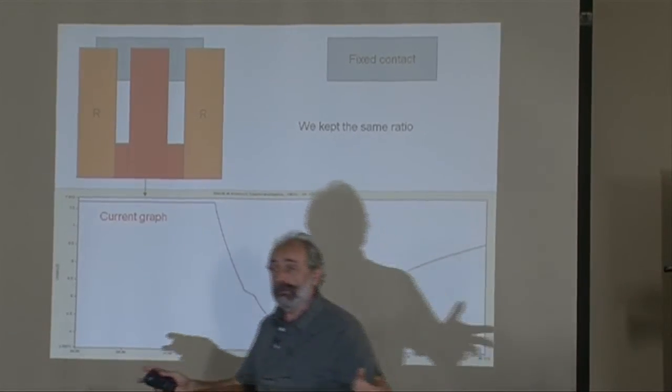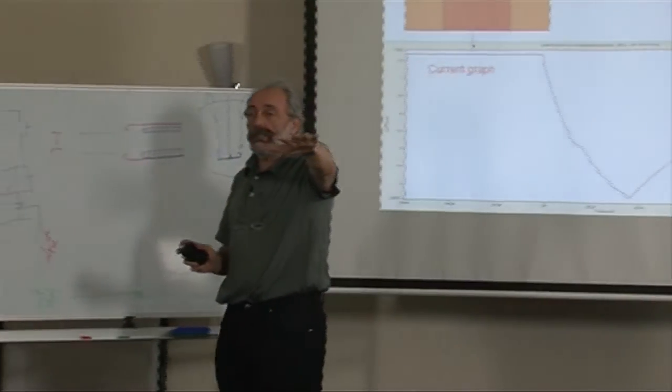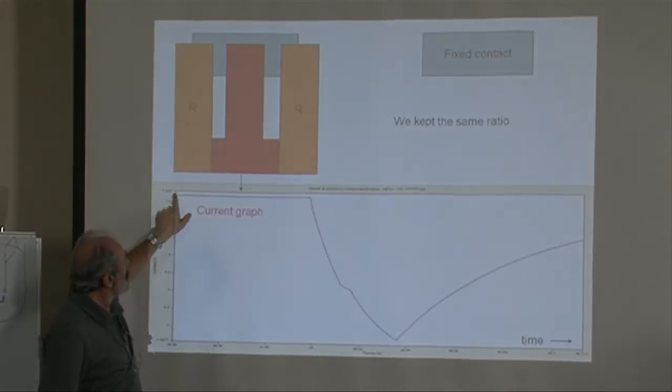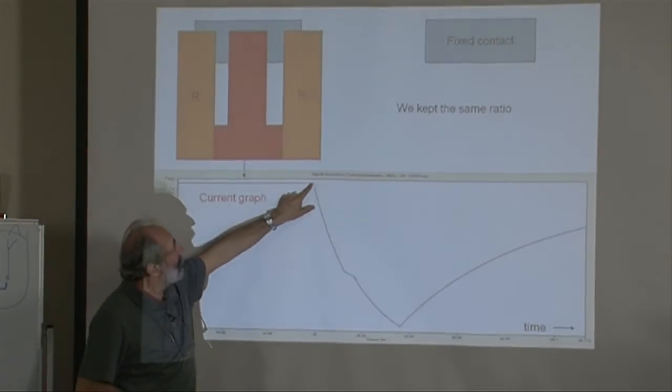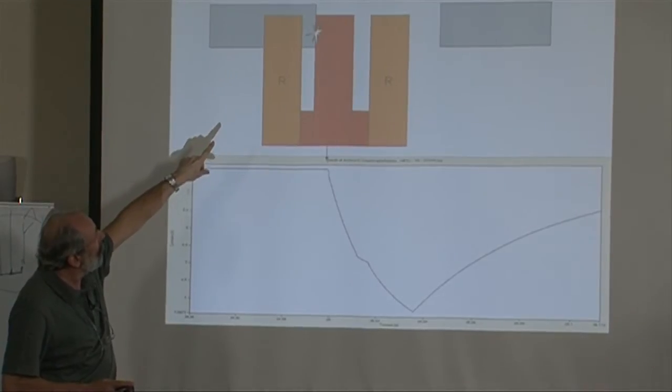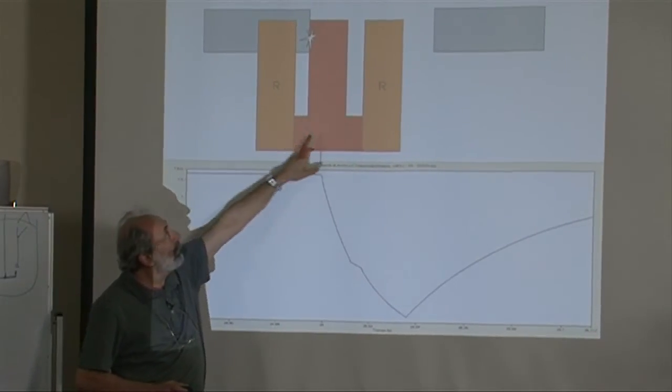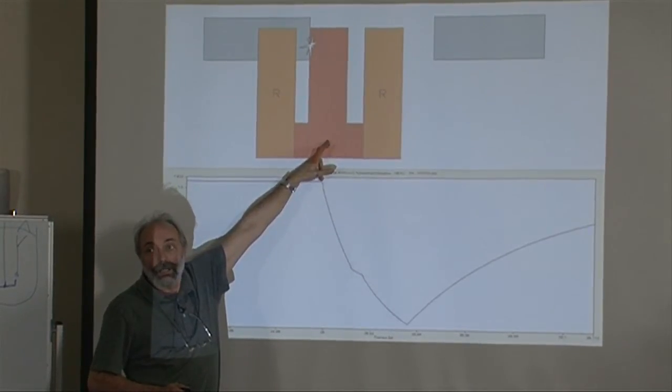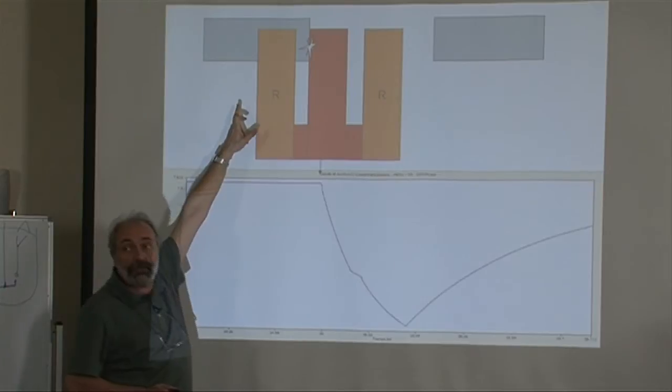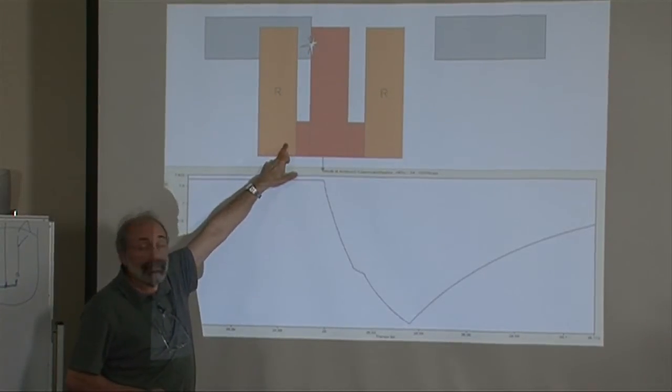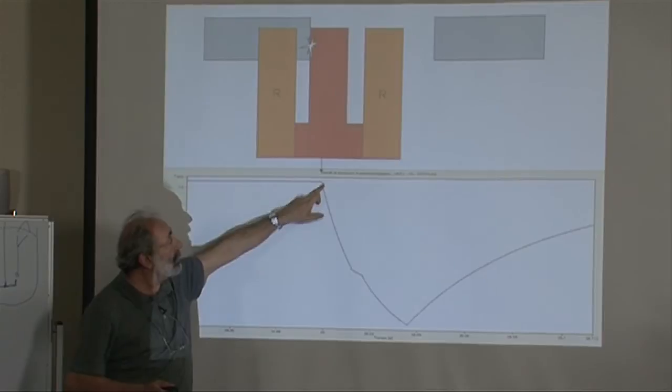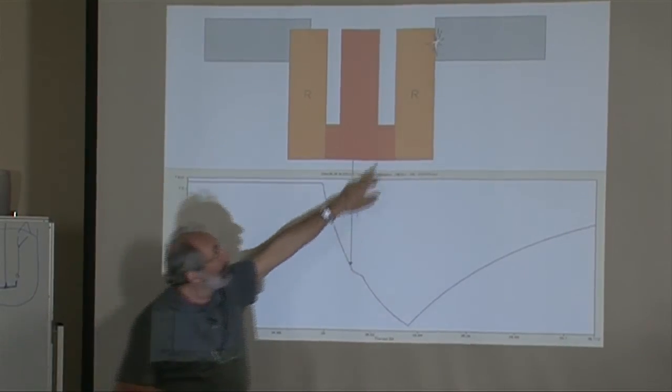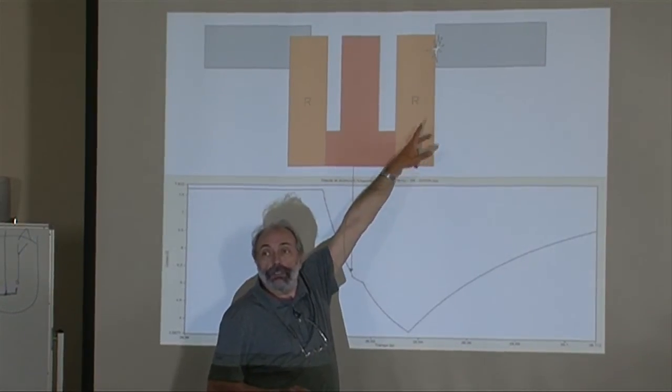If we measure a winding resistance, we run a DC current through winding. And we have a current. It's a nice stable current. So if we start moving what happens is the point when the main current carrying contact parts from the fixed, all the current goes through resistance. If it goes through resistance it drops. And it drops all the way until this roller touches with the next contact.